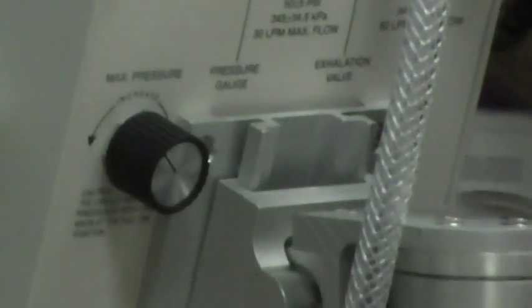The other thing back here is the max pressure knob. What's important about this, when you're setting it up, is you want to turn it up. If it's turned down too low, you may think you're set at a volume, but you're pressure limiting. We're going to use this as a safety pop-off a little bit later, but I want to make sure that when I set up my breath, I can get the full volume. So I'm going to turn it all the way up.